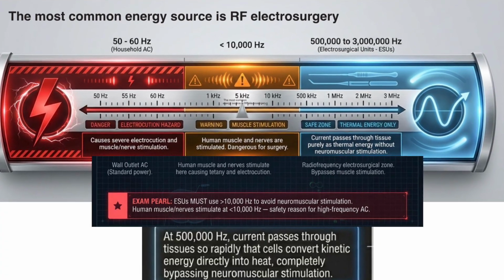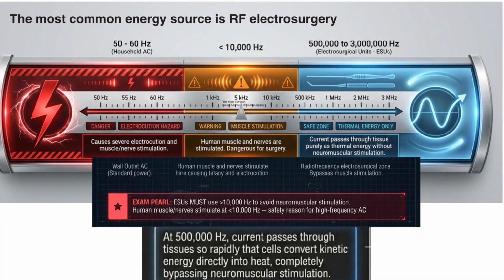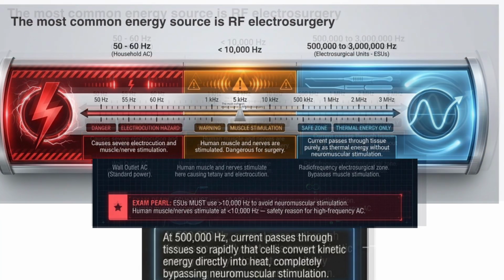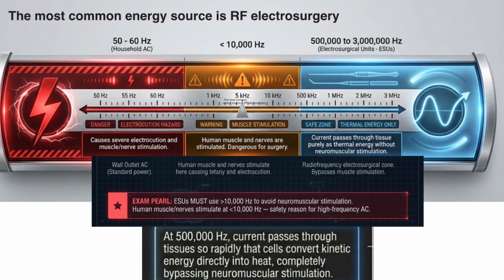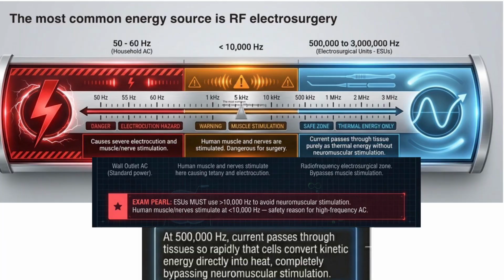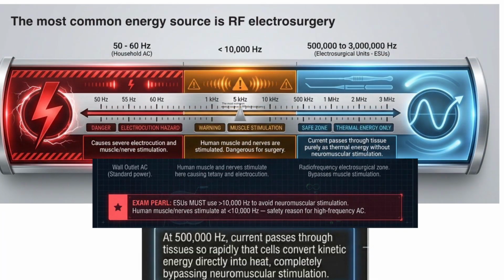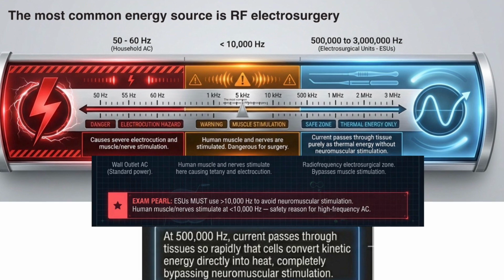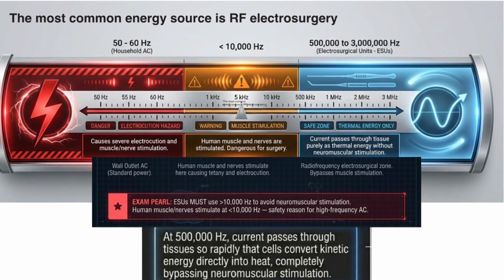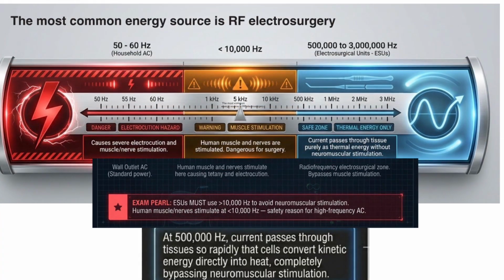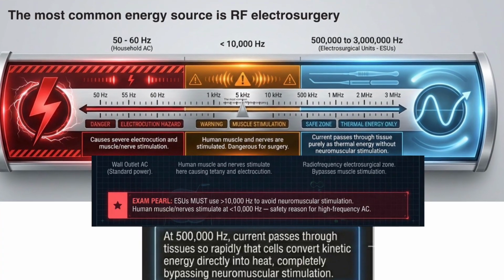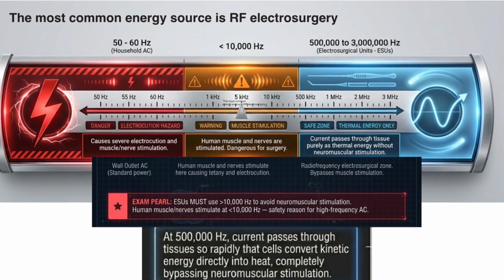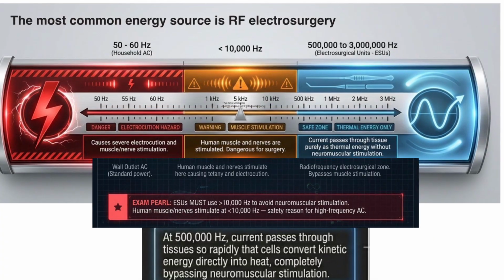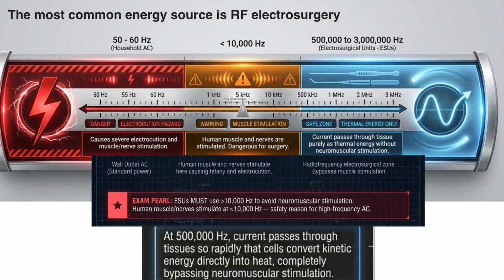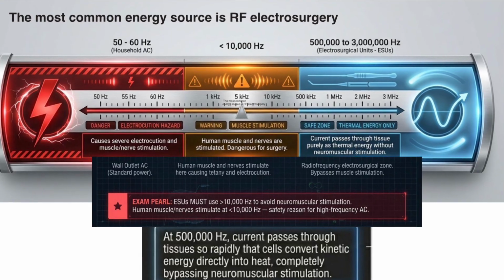50 to 60 Hz is the household AC current, which is the wall outlet current and is a standard power. At less than 10,000 Hz, when it passes through the human body, it stimulates the nerves and muscles, which is dangerous for surgery as it causes tetany and electrocution. When the frequency is 5 lakh to 30 lakh Hz, it is suitable for surgery. The current passes through the tissues purely as thermal energy without neuromuscular stimulation. As it passes through the tissue so rapidly, the cells convert the kinetic energy directly into heat and neuromuscular stimulation is completely bypassed.